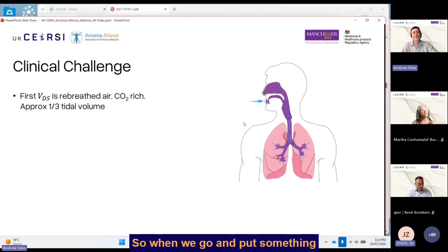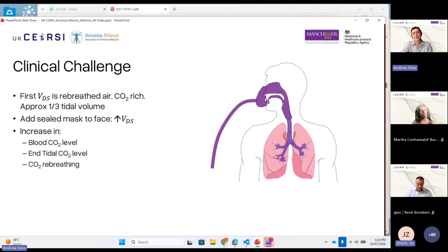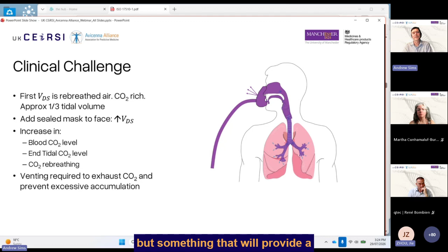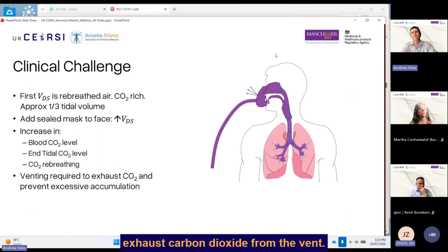So when we put something on our face, like a CPAP mask, we've increased that dead space. The result is there's a potential to rebreathe more carbon dioxide, and that needs to be managed. That can result in an increase in blood carbon dioxide, exhibited in your end-tidal carbon dioxide and increased carbon dioxide rebreathing. So this needs to be mitigated in the mask by the incorporation of a vent, so that we can maintain pressure, not have a whopping great big hole there, but have something that provides a controlled venting and allows us to exhaust carbon dioxide from the vent.